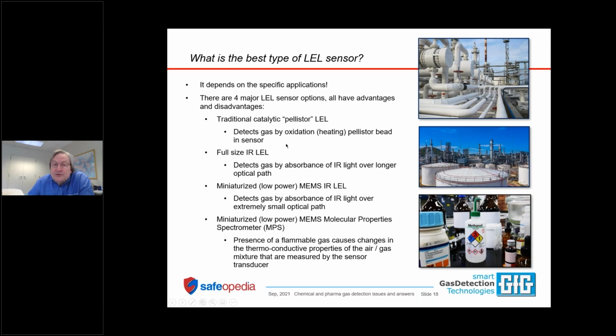Your options besides the catalytic LEL sensors are IR LEL sensors. They come in full-size version with a long optical path. These kind of sensors require a little bit more power, but they are better for dealing with olefins and unsaturated and aromatic hydrocarbons and VOCs. IR LEL sensors can never ever be used to measure hydrogen, and the ones in portable instruments are not able to detect acetylene either. So if you have either of those two gases, then you need to make sure that one of the other sensors in the instrument is going to be capable of picking them up. The full-size IR LEL sensors are really good at measuring unsaturated as well as saturated type hydrocarbons and alcohols.